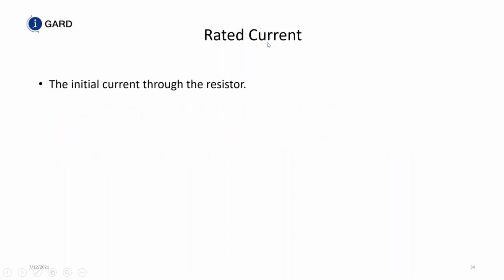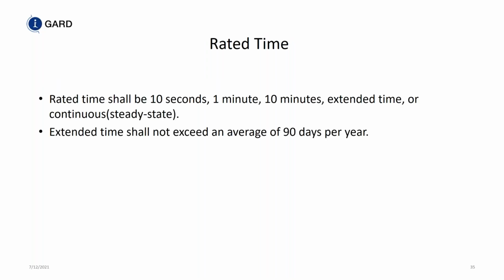Rated current is the initial current through the resistor, not the rated current through the resistor, the initial. What happens to the resistor when you first have the fault on the system? What is the maximum current you can get? And we're going to get to why that is. Rated time under IEEE C57.32 is 10 seconds, 1 minute, 10 minutes, extended time, or continuous duty. Extended time shall not exceed an average of 90 days per year. According to CSA, 10 minutes and extended time are not recognized as rated times. That may change in the future, but for now, you cannot have a 10-minute rated resistor nor an extended time rated resistor under CSA.